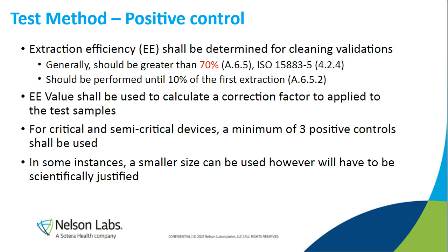And 70 has been historically thrown out in USP, in ASTM, so when you see this number, you will resonate with the number like, yeah, this is common that we see. But it wasn't established for reusable medical devices. They didn't extrapolate to that. But now we have that, and you will have to meet greater than 70% extraction efficiency, where you would apply this to your test samples as well.